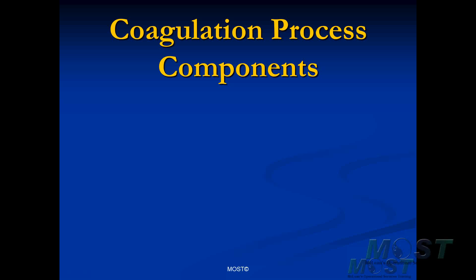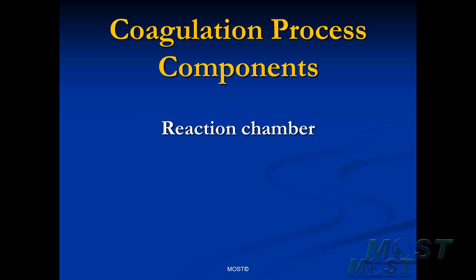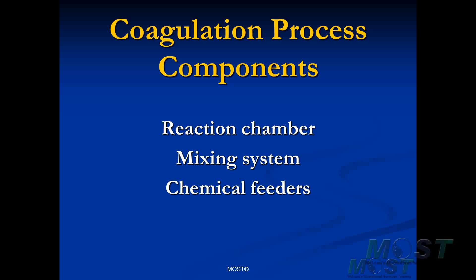To accomplish coagulation, we need a system with at least three components. These key components are a reaction chamber, a place where the coagulation process can actually be performed. Secondly, we need a mixing system so that the incoming raw water can be thoroughly mixed with our primary coagulant. And finally, we need a chemical feeder that is capable of accurately dispensing precisely the amount of chemical that we need to accomplish coagulation.